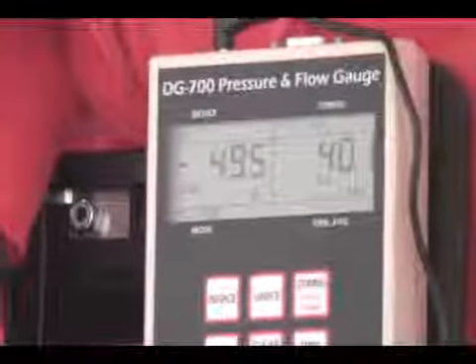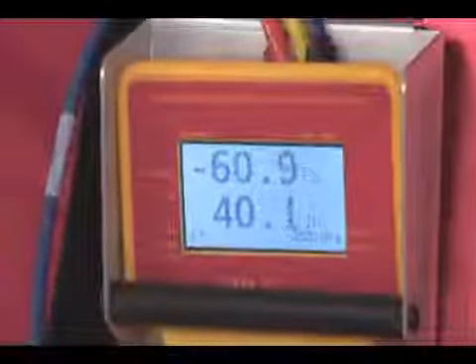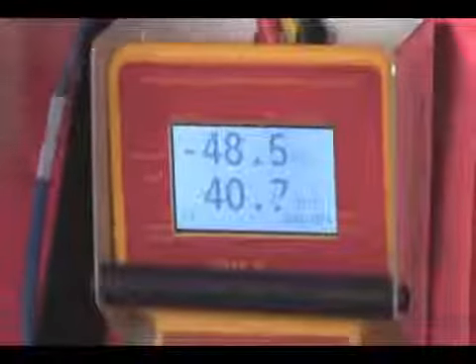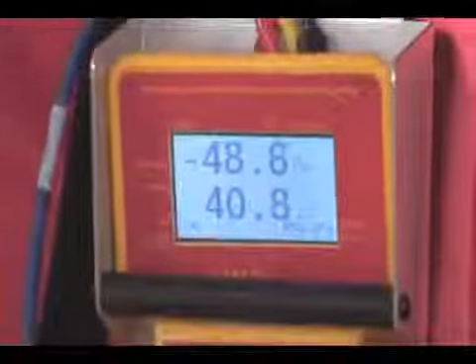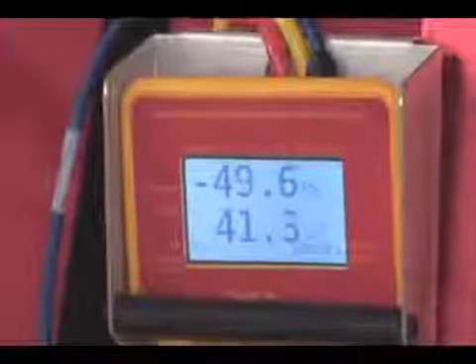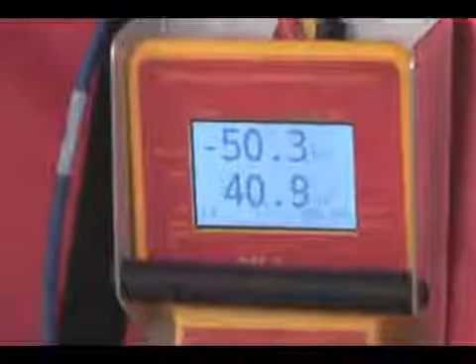So we've got at least 32 and maybe another 8 here and there. A very similar situation we have with this system over here. Here we can put this on auto zero, and we've got square inches at 50 pascals. Here we do it slightly differently — we go set pressure, 50, enter. We have a very similar result. Again, we've got square inches at 50 pascals. We have the same holes opened in this simulator, so we're also running around 40 square inches — the 16 square inches that we know about on each side for 32, plus another miscellaneous 8 square inches or so here and there.